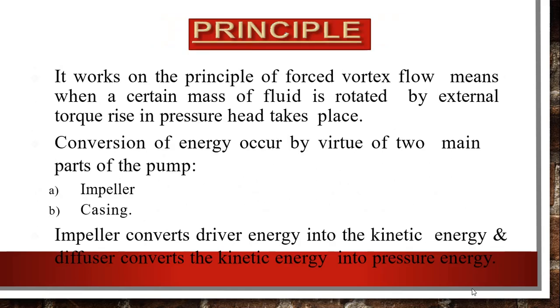Centrifugal pump works on the principle of forced vortex flow, meaning when a certain mass of fluid is rotated by external torque, the pressure head inside the casing rises. The conversion of energy occurs by virtue of two main parts: the impeller, which converts driver energy into kinetic energy, and the diffuser inside the casing, which converts kinetic energy into pressure energy.